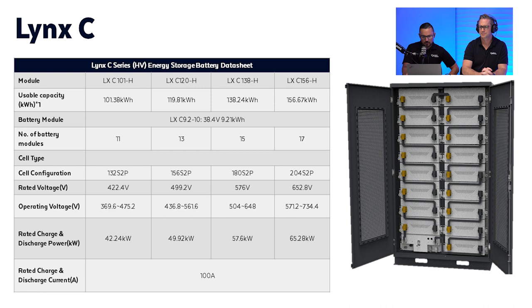So here are just some specs, showing you the inside of the cabinet. With this Lynx C-type series, the smallest option is 101 kilowatt hours. That pairs quite nicely with the 50 kilowatt three-phase hybrid. One cabinet can go up to 156 kilowatt hours. And just remember, you can have up to three of those in parallel.